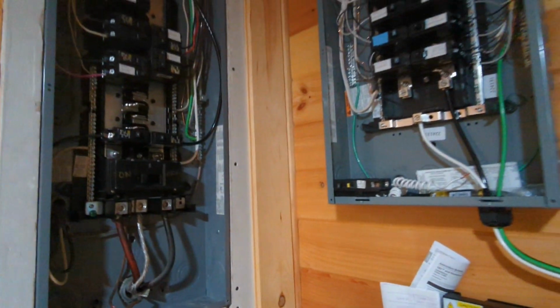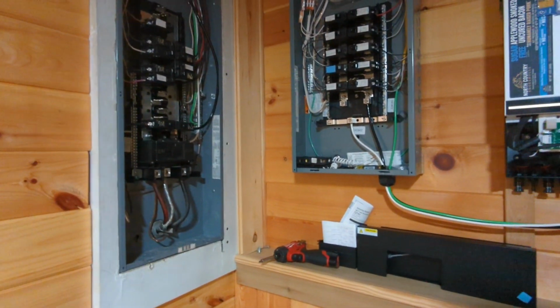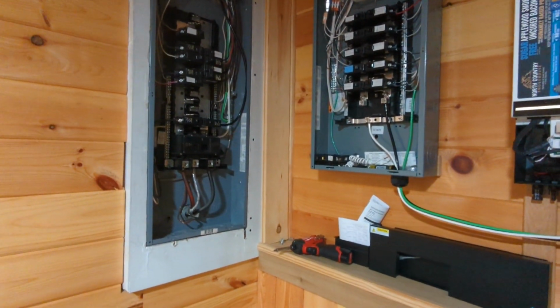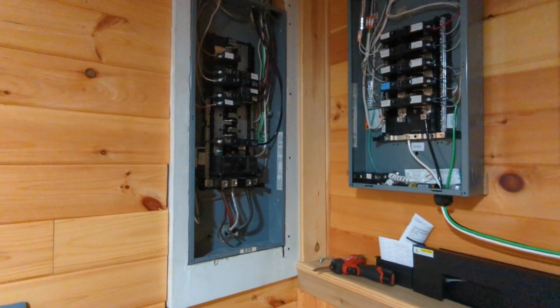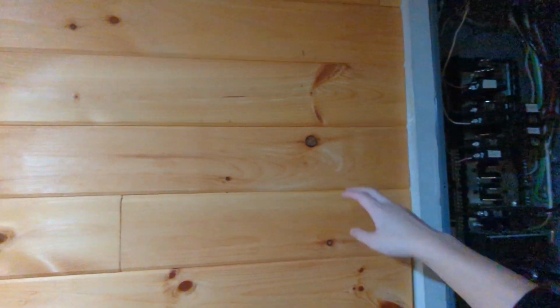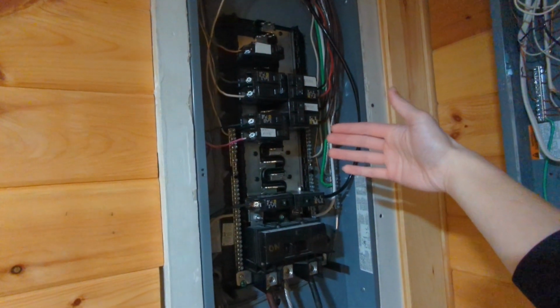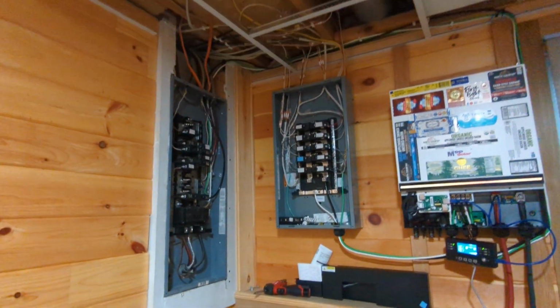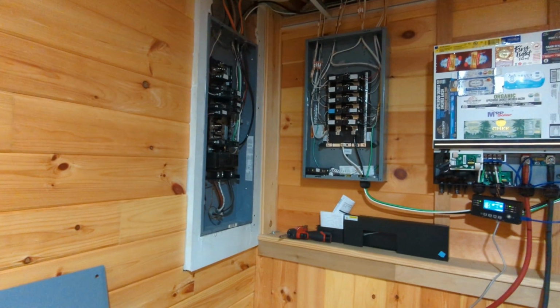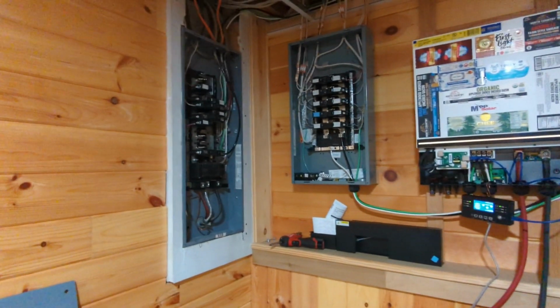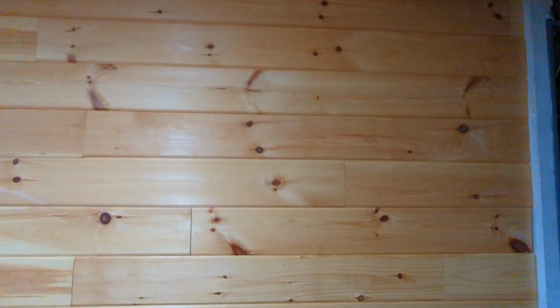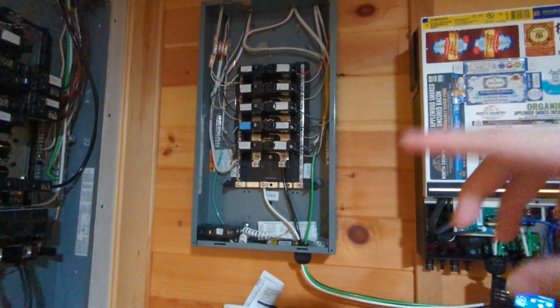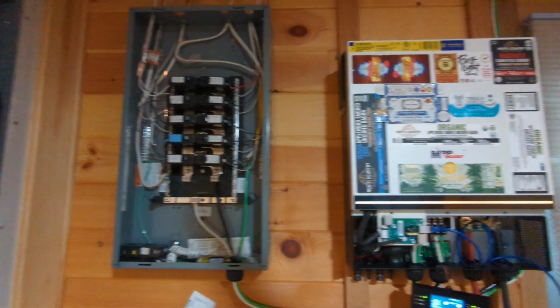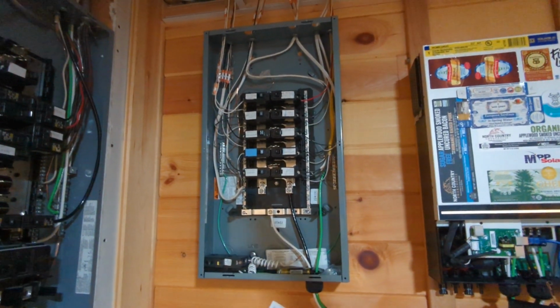If I ever do get a second inverter where I can run the 240 volt split phase for all the 240 volt loads, if I do decide on doing that, I will put the second inverter just about right here next to the original panel. That way, I'm thinking this kind of layout would be the most efficient use of the space in this part of the house along these 2 walls. The other option was to have both of these inverters right here on this wall next to each other, and then this single load center panel would probably be closer to the middle of this wall, or maybe I could just have it exactly where it is right now.